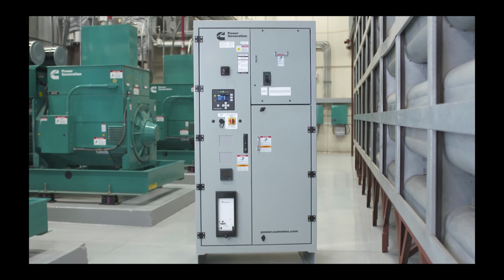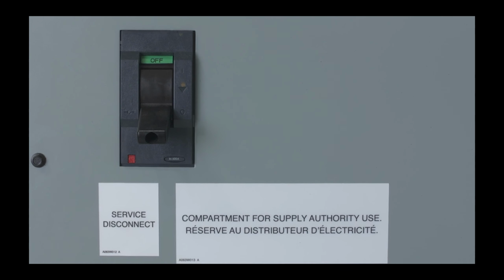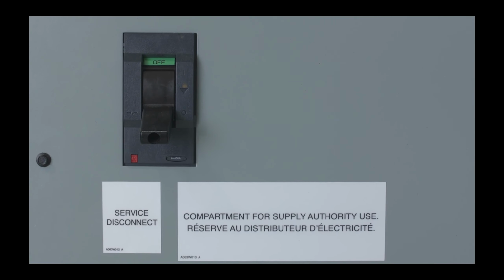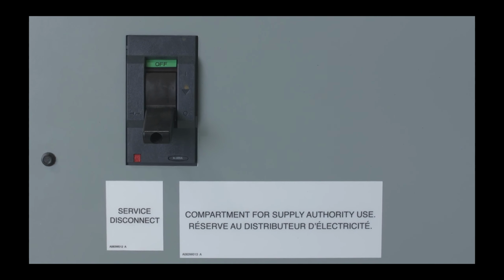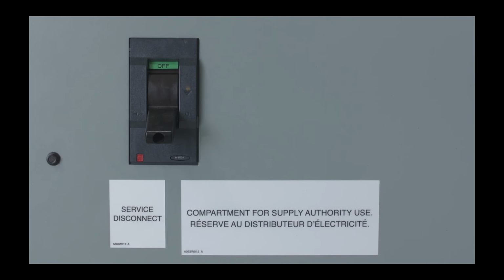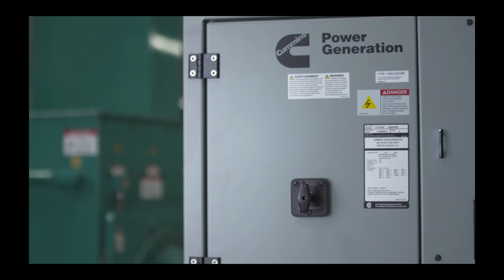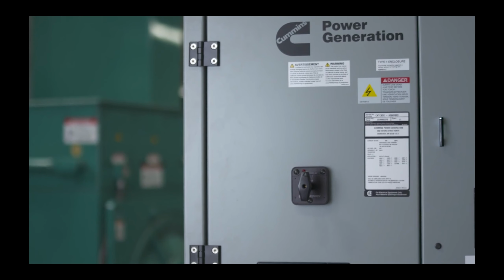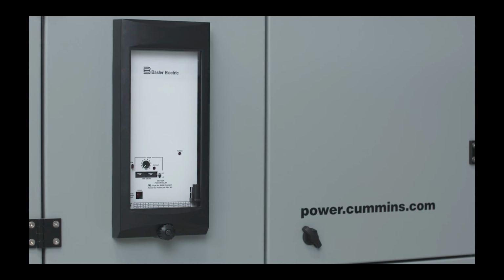This C-frame is a service entrance rated transfer switch, which means it is equipped with an integrated OCPD, overcurrent protection device, a circuit breaker, for isolation in case there is a need for a fire marshal or a facility operator to disconnect power to the facility for any reason. Also, as you can see, there is an 86 lockout relay and a 32 reverse power relay needed for closed transition intertie agreement with the utility.